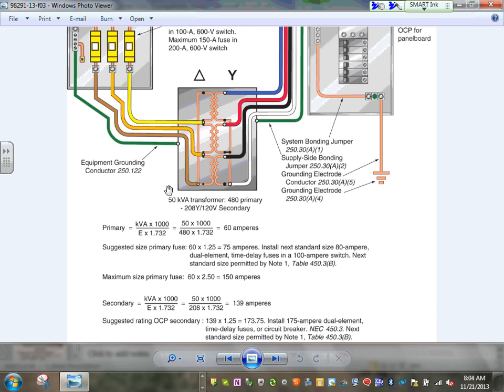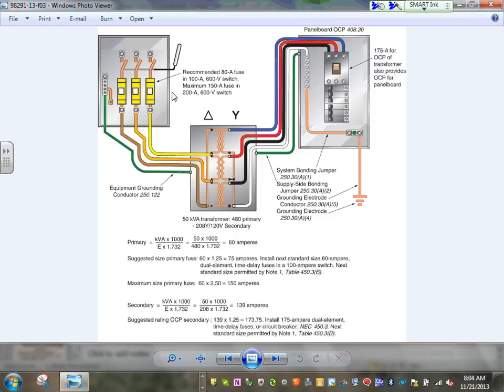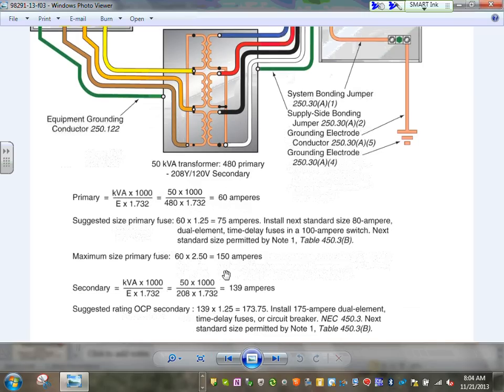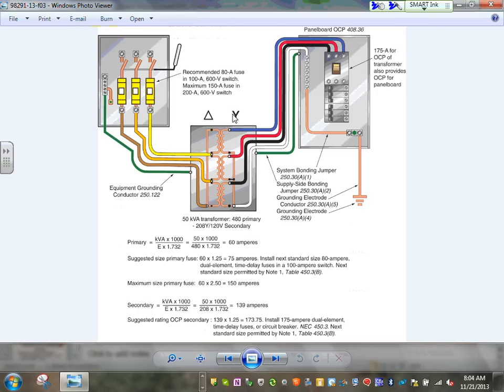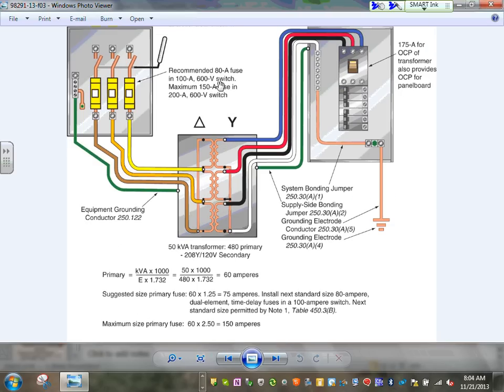Here's how they do that. Here's an example, guys, of how we size the transformer. Very quick example. You take the full load current of the transformer on the primary, you multiply by 1.25 because of the voltages. It looks like 600 in both, less than 600 both ends. And then you multiply by 1.25 and you go to the next standard overcurrent protection device. On the primary side, maximum size fuse on the primary. You size your conductors based on 1.25 and your overcurrent protection device based on 2.5. The secondary side, you size your conductors and your overcurrent protection device based on 1.25. Again, we will do this one, guys. We'll do the same example. The rest of you guys, when we have a 4,000 amp switchgear in the industrial project, you will have the exact example, and you need to size the conductor for it, based on the table. So we'll do that one, guys, in detail.